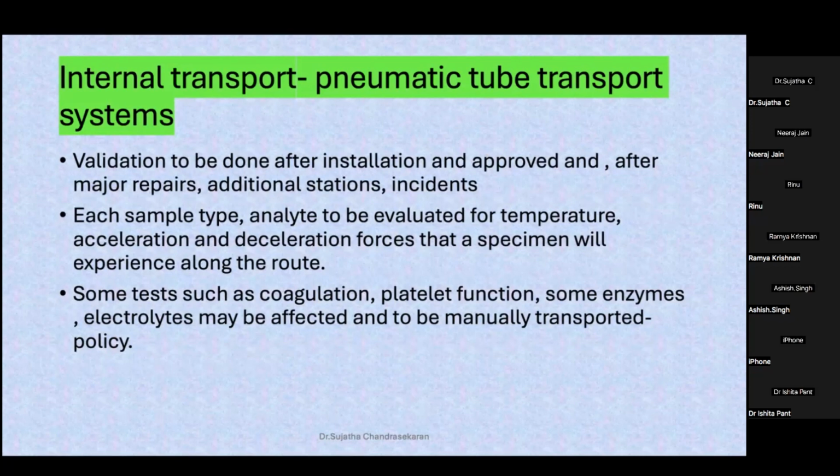This is entirely different from another hospital, which is vertical. The samples may drop from the 20th floor to the lab, which is at the basement, or vice versa, from a collection which is on the first floor to the lab, which is on the 14th or 15th floor. The pressure requirements for the pneumatic tube are entirely different. And these pressures, there is an acceleration, deceleration, and the G is the engineer's problem. They do the G value during their annual maintenance to make sure that there are no vacuum leaks and the G values are maintained.